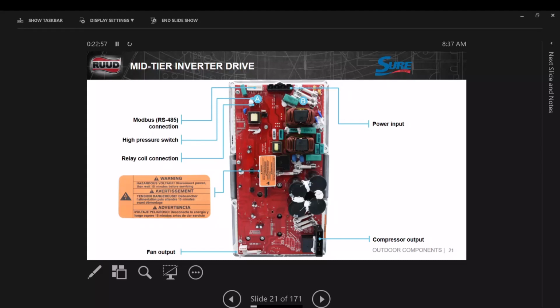And what basically happens is if you do push the contactor in, it takes the power from the inverter and the power from the contactor and capacitor and puts it together. And that feeds back into the board, burns the board out. And that's not covered under warranty.